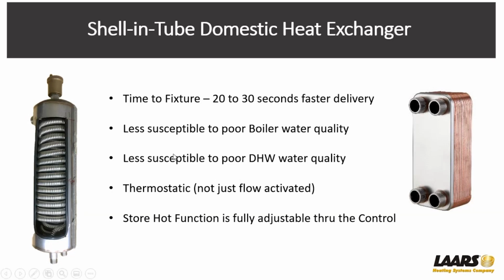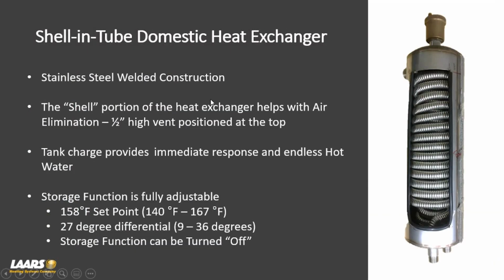And stored hot water function is fully adjustable through the control. And we'll get into that in a minute. So again, it's all stainless steel welded, no gaskets. The shell and tube portion of the heat exchanger helps with air elimination. Why? Because we have a 1/2-inch high vent right on the top of the domestic heat exchanger. So any air would be removed right there. Tank charge mode provides immediate response. So again, that was time to the fixture of endless hot water. And again, storage function is fully adjustable. And what we're referring to is the hydronic boiler water in the vessel.